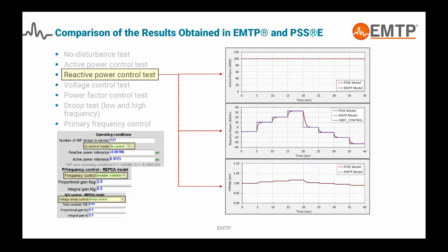For the reactive power, the same thing. You can play with the reference in terms of reactive power, and you can see that both models respond very fast according to the settings in the controllers, right? And even the voltage measured at the POI responded very similarly.